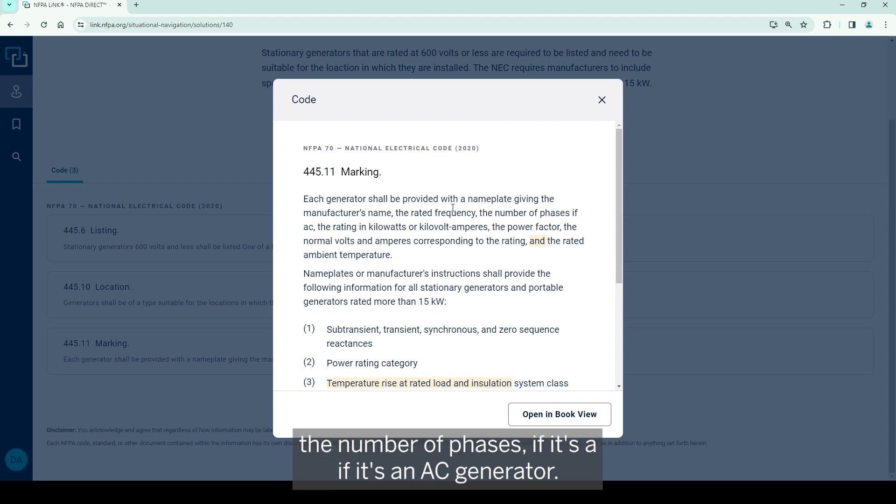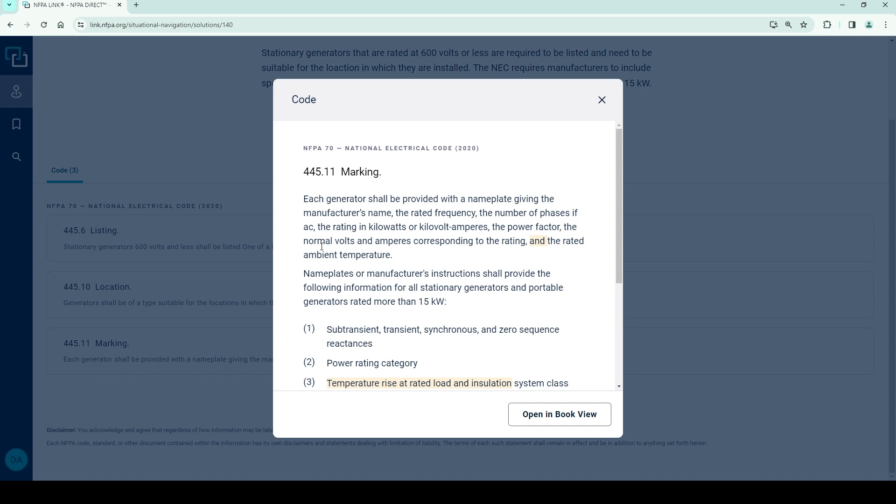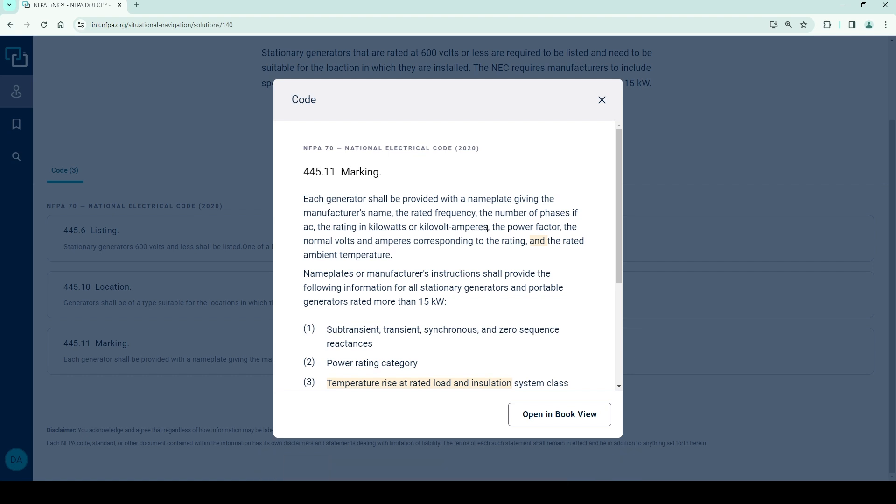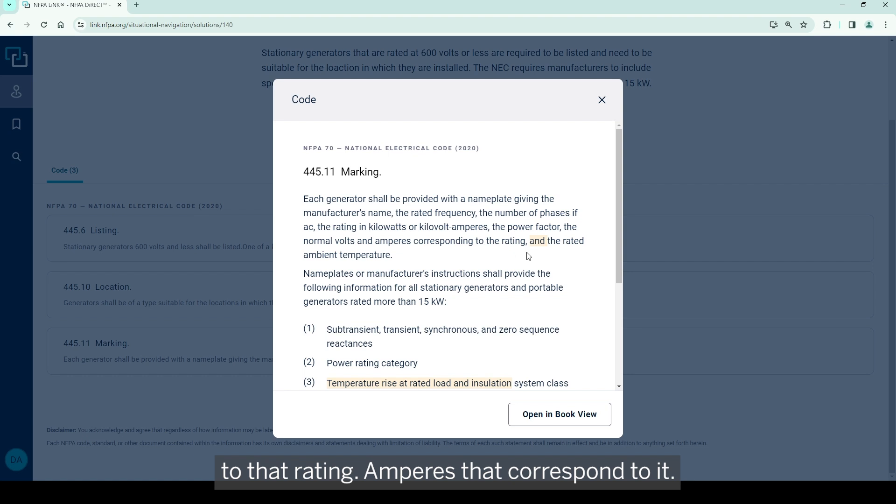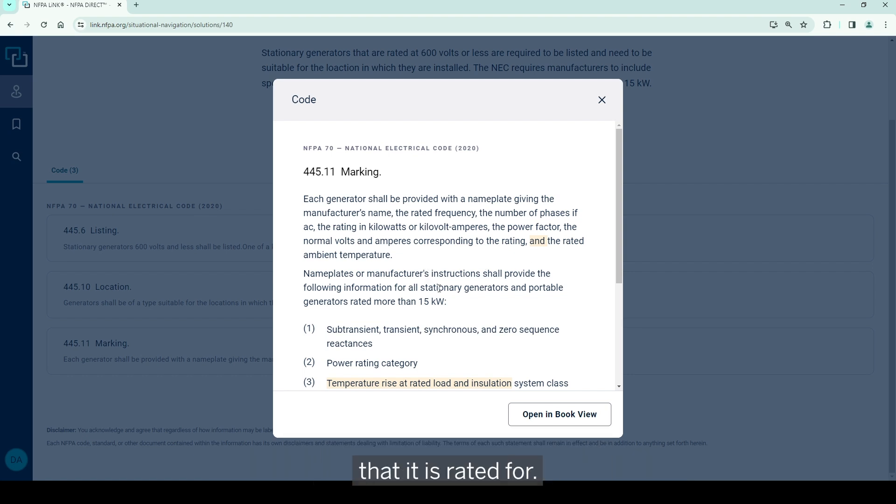The number of phases if it's an AC generator, so single phase or three phase, rating in kW or kVA - the kilowatts or kilovolt amperes - needs to have the power factor, the normal volts and the corresponding amperes to that rating, and then of course the rated ambient temperature that it is rated for.